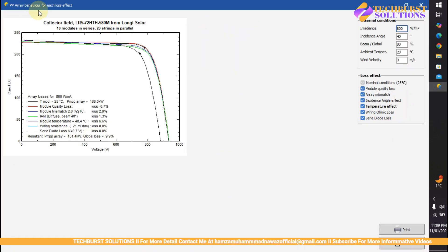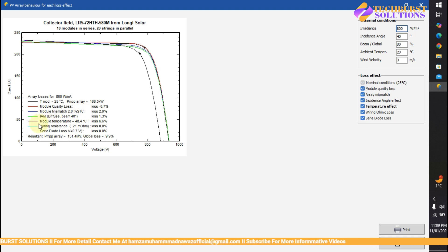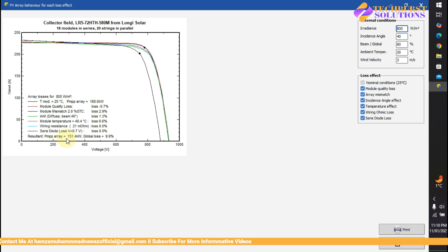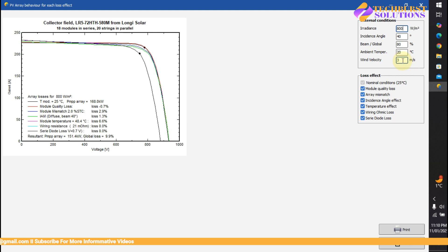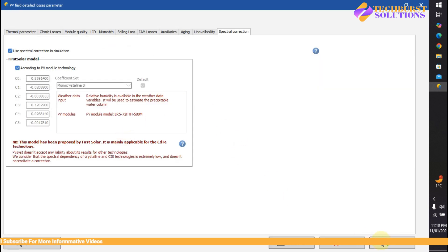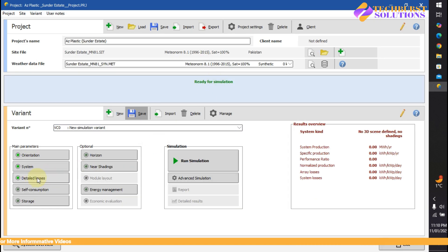For PV array behavior for each loss effect: temperature effect, module quality loss is 0.7 percent, module mismatch is 2 percent at STC, module temperature is a loss of 6.6 percent, wiring resistance is 21 milli-ohms, and serial diode losses are minimal. The result shows P-maximum array is 151 kilowatts, global loss is 9.9 percent, irradiance is 800 watts per square meter, incidence angle is 40°, beam ambient temperature, and wind velocity is 3 meters per second. We've completed the detail losses section. In the next video we'll discuss other things — take care!